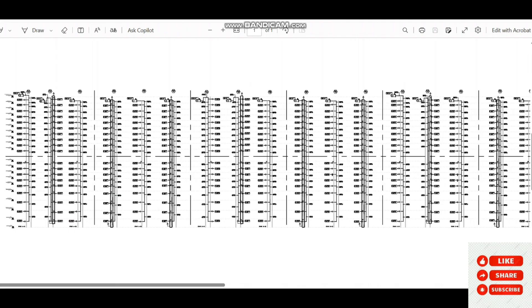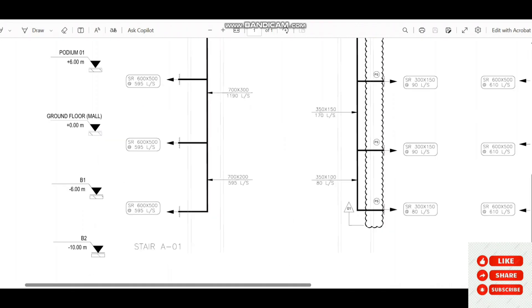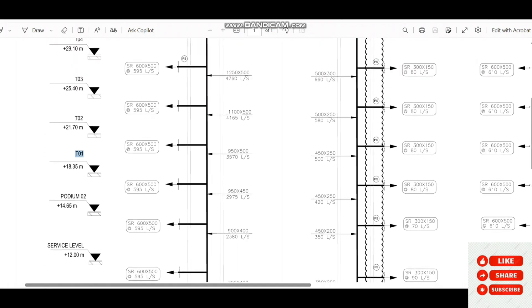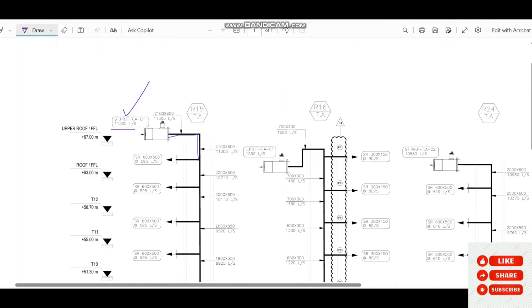This high-rise building project has plenty of staircases and lift arrangements. The concept for each is similar. At the top level we have the staircase pressurization fan with a capacity of 11,305 liters per second. The duct supplies air to each level from basement 2 up through basement 1, ground floor, podium levels, service level, podium 2, and floors 1 through 12, with roof and upper roof at the top. Before proceeding, we must understand some basic and important requirements of NFPA 92.